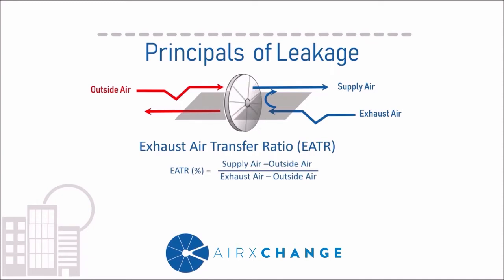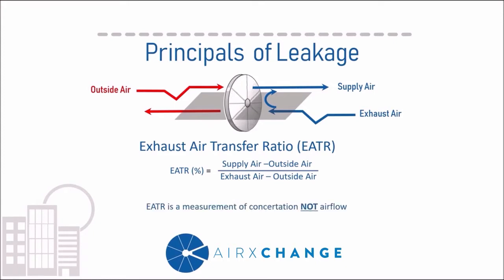EATR is a value represented by a percentage. When this value is determined during testing, it's determined by measuring the concentration of a tracer gas at three points of delivery. EATR is a measurement of concentration, not an airflow measurement. By using a concentration, it allows you to measure and calculate a value that is independent of material and process — meaning the value is based upon all influences that would encourage a component of the exhaust air to be delivered into the supply air.